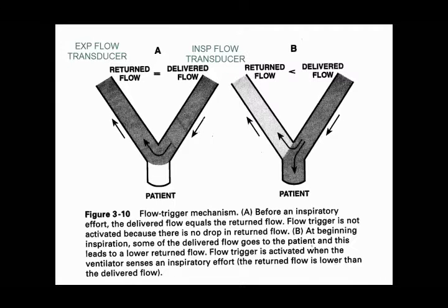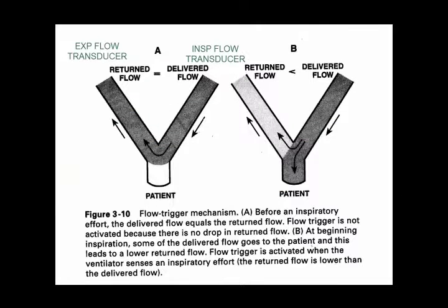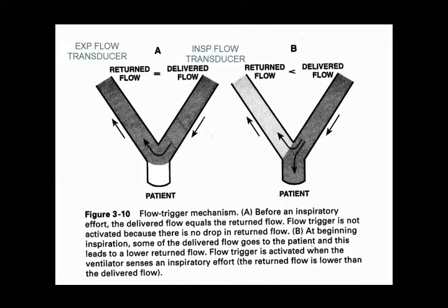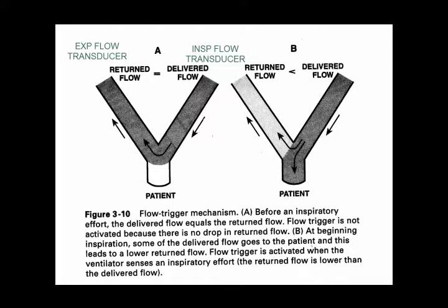Pardon me? Yep. So it kind of goes in line with the sensitivity as the patient is initiating or assisting, doing the assist, it's generating the flow for the breath. Instead of using pressure as the criterion, I'm using a change in flow.